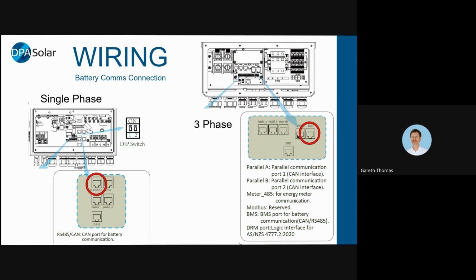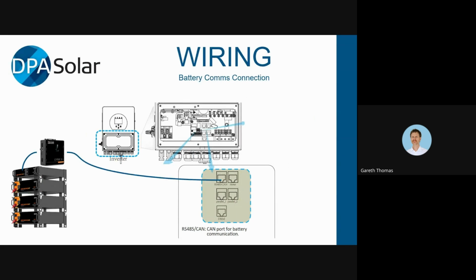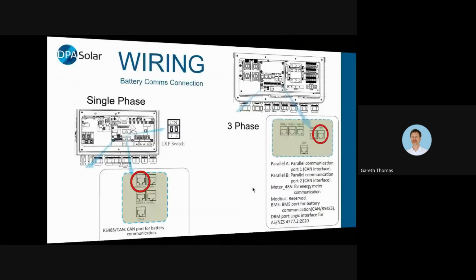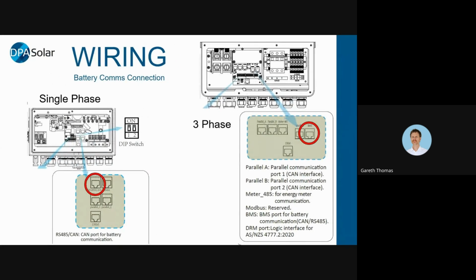And for those who are interested, if you ever wanted to talk to the inverter via Modbus RTU, that's done over the RS485 style connection. You can actually have the CAN bus and a Modbus connection on the same RJ45 plug. You just have to split out the cable because they're on different pins. If anybody has any questions, just put them in the messages.